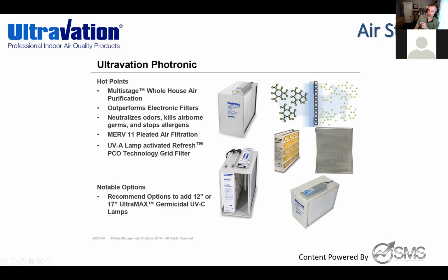So we made it scalable. If you order it with the accessory of adding on 2 UVC bulbs, which you plug into the power ballast and put on the coil, that's what helps this solution align with ASHRAE guidelines—because now I'm putting UVC wavelength bulbs into an HVAC system, so I'm putting UVGI on the coil. That's how you take a solution like this, scale it up, and still align with ASHRAE guidelines. This is really targeted at airstream purification, dealing with the returning air before it even gets into the system. When you add the optional bulbs, you're now also dealing with the coil. So this is one solution for airstream, really focused on return before the equipment.